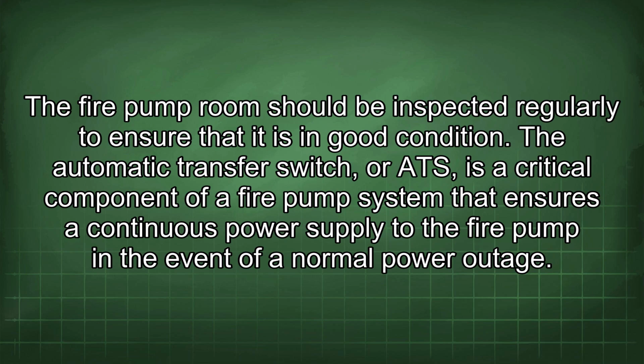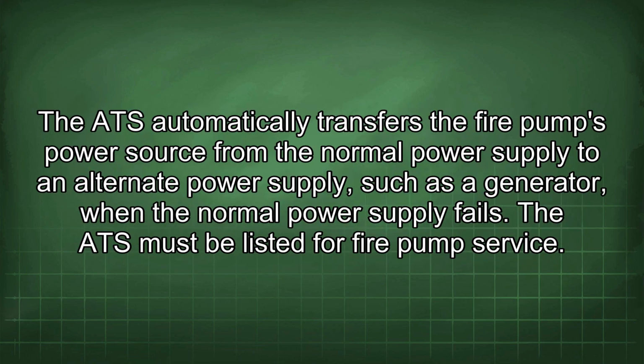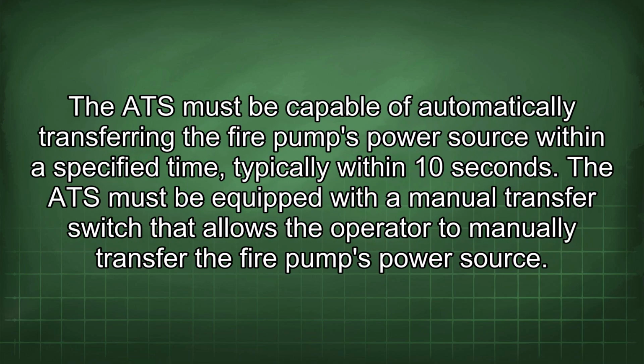The automatic transfer switch, or ATS, is a critical component of a fire pump system that ensures a continuous power supply to the fire pump in the event of a normal power outage. The ATS automatically transfers the fire pump's power source from the normal power supply to an alternate power supply, such as a generator, when the normal power supply fails. The ATS must be listed for fire pump service. The ATS must be capable of automatically transferring the fire pump's power source within a specified time, typically within 10 seconds.